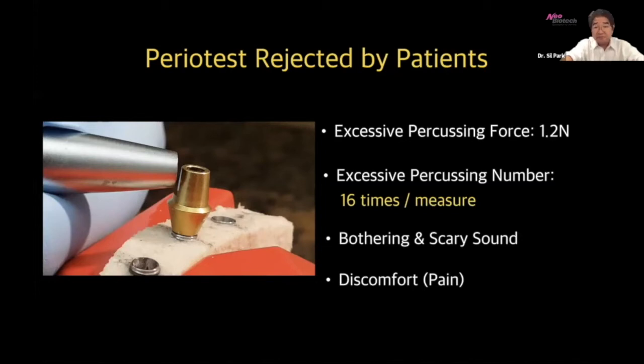Also, based on my humble research experience, the Periotest can compromise actual implant stability. So the doctor doesn't like it and the patient doesn't like it. The Periotest is still on the market, but nobody buys it except people like me who do research. So I do not recommend using it, because in clinical situations it is very difficult to use.